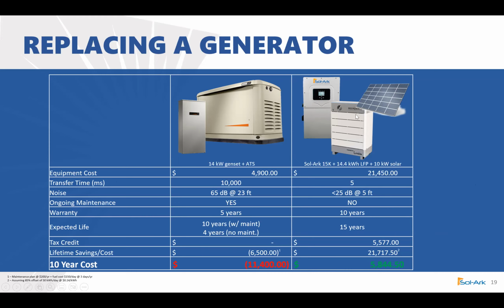First, the transfer time. Our inverter has a 5 millisecond no-glitch transfer time. That means the second you lose grid, your lights are not even going to flicker, your clocks aren't going to reset, and if you have important IT server rack equipment, it's going to continue to run. Now, a whole home generator has a 10-second transfer time. Your lights go out, you wait, the ATS triggers over, the generator starts up, and 10 seconds later you'll have power. Next, we'll compare the noise.